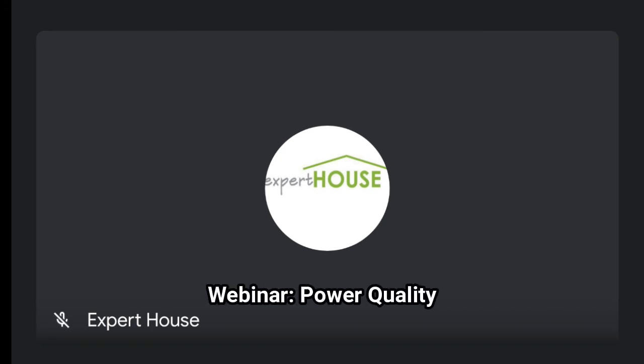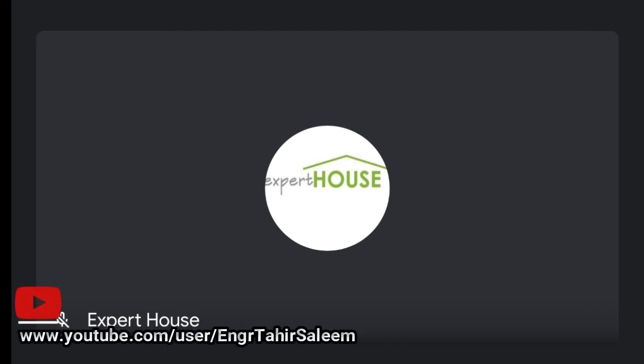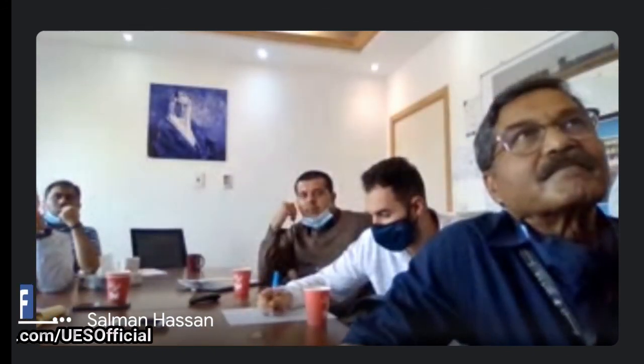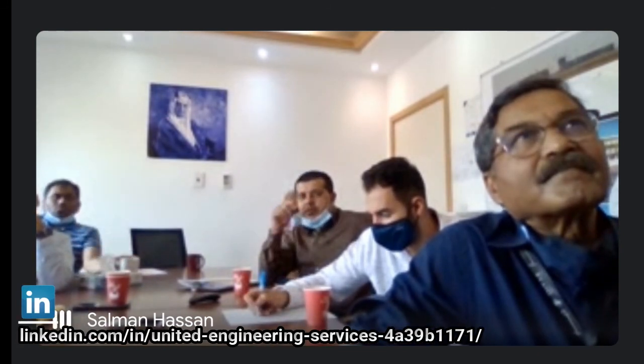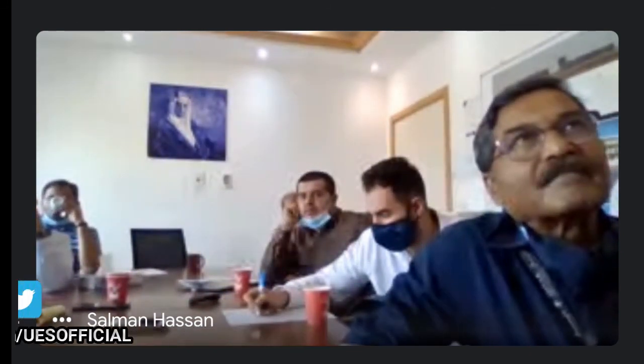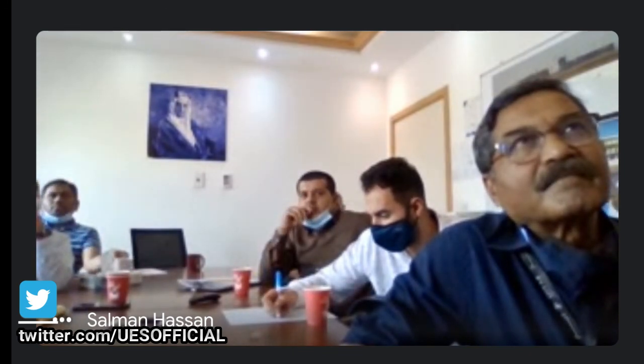And what to do at the consumer end? Somebody told me that, like low power factor, penalties are imposed in different countries, and they also impose limits on harmonics. If your harmonics are not within certain limits, because they destroy the power supply system, they impose a penalty like they do for power factor. Yes, in Pakistan the limiting value for power factor is 0.9, and if it is less than 0.9, they impose a penalty.